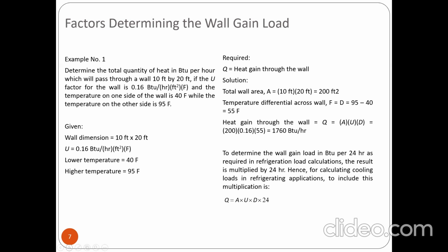Solution. Find the total wall area: 10 by 20 is 200 square feet. The temperature differential across the wall is D equal to 95 minus 40 or 55 Fahrenheit. And the heat gain through the wall is Q equal to A times U times D, or 200 times 0.16 times 55, which is 1760 BTU per hour.